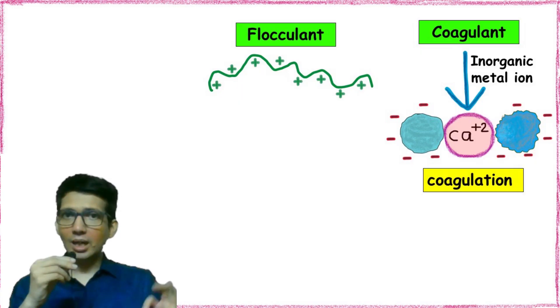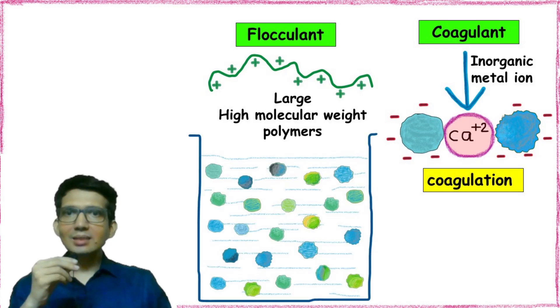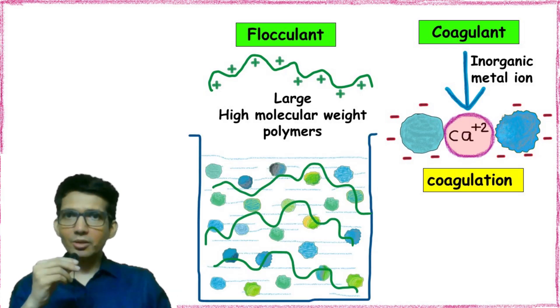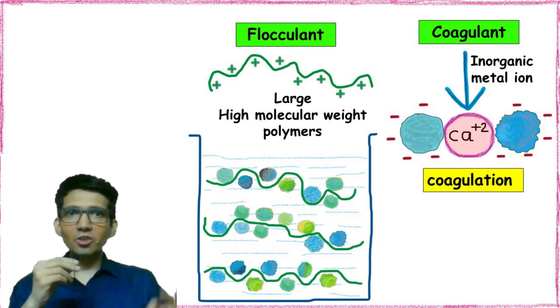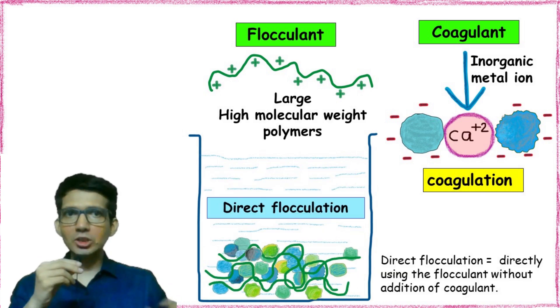The flocculants on the other hand are large high molecular weight polymers which can be chemically synthesized or they can be biological. The use of these high molecular weight polymers to cause aggregation of particles is termed as direct flocculation, i.e., we are directly using the flocculant without the addition of coagulant.